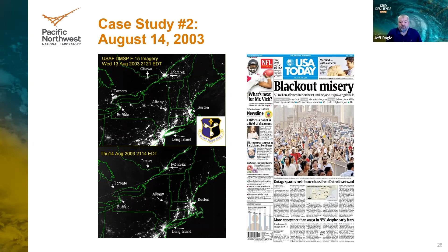This is a diagram that shows the hours leading up to the blackout. The blackout occurred just shortly after 4 o'clock in the afternoon. But the real key event, even though there's a power line that tripped earlier in the day called the East Lake 5 unit, the real important thing happened right after 3 o'clock. That little line called Harding-Chamberlain tripped at 3:05, which created a condition where the system was no longer safe to additional outages that might occur.